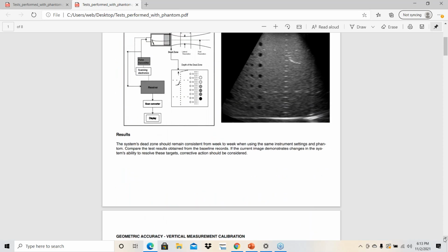And then the results, it tells you the system's dead zone should remain consistent from week to week. So really all these phantom tests have the same kind of description at the end. They're looking for degradation over time. You either have degradation or you don't. They should remain consistent week to week, month to month. And when you find something that has significantly changed, or maybe not so significantly, but you can start to see a pattern where it's degrading over time, then there's something coming up, and you could be aggressive, you could be proactive in solving it. So that's the first test, dead zone test, pretty simple, and it has to be done for every probe.